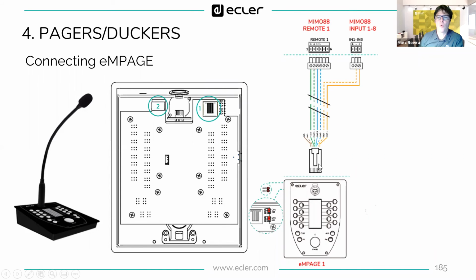So you have to connect this RJ45 to the unit and take care of this wiring to connect the unit correctly. As this unit is also used in other devices, you have to check the jumpers inside. In fact, you don't have to check, you have to change it. By default, they come configured for other devices. So you have to change and put this configuration.